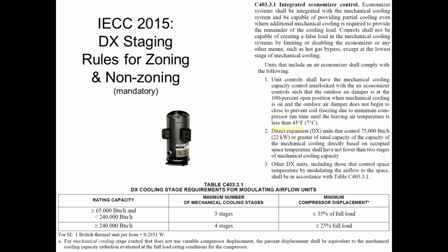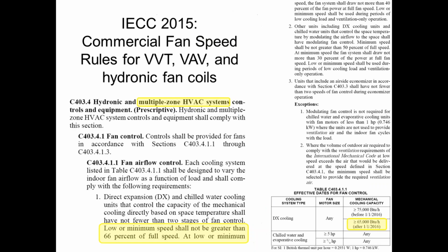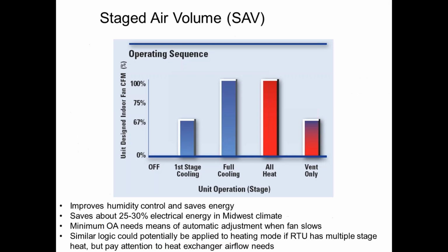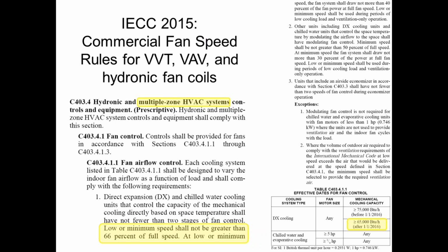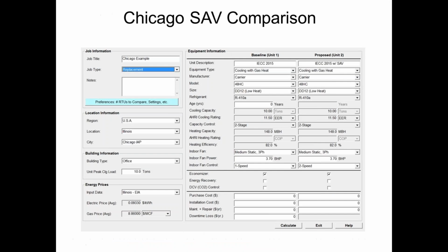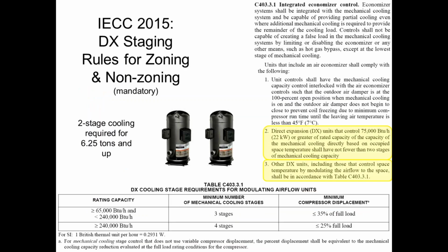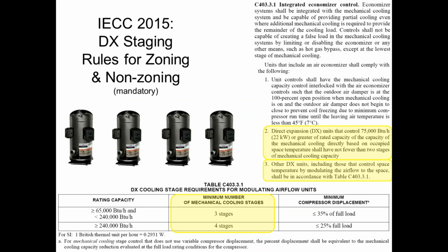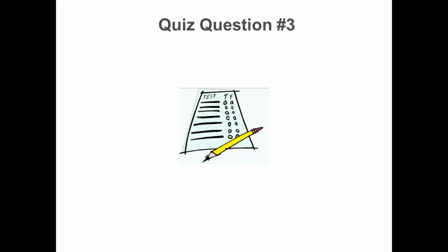Which then would mean anybody that was doing the 2-speed fan would hence also have to do the 3 or 4 stages of compression. So I don't think you want to interpret it that way, but either way, if you did, it's still going to be linked back to having a zoning system or a hydronic coil. So it ends up being the same discussion no matter which way you want to literally interpret that language. As soon as you put zone dampers on, plan on having 3 or more stages of cooling compression. I've got a feeling that this one will start evolving into more and more units, not just zoned units. But right now, it's just zoning only.